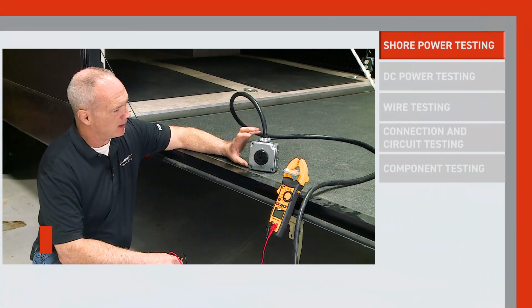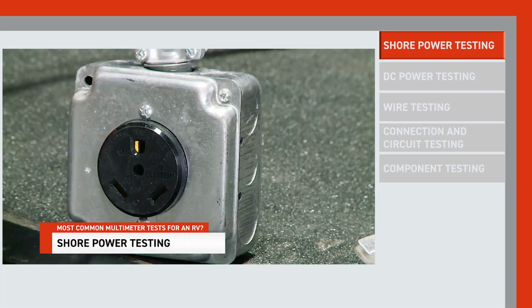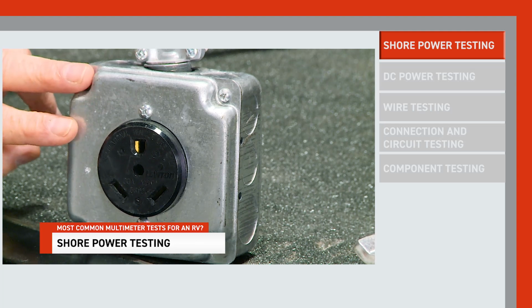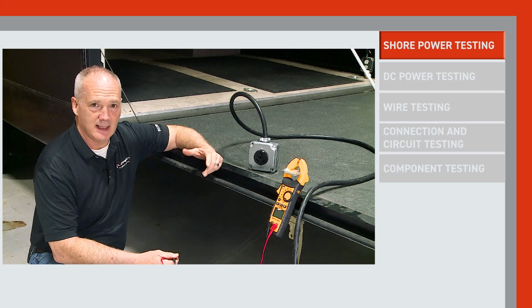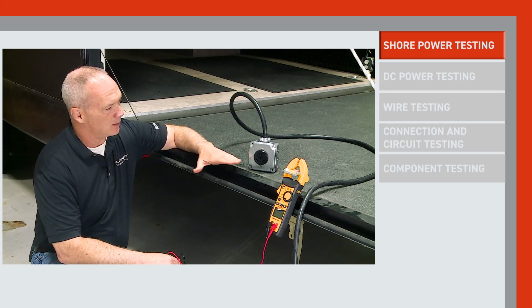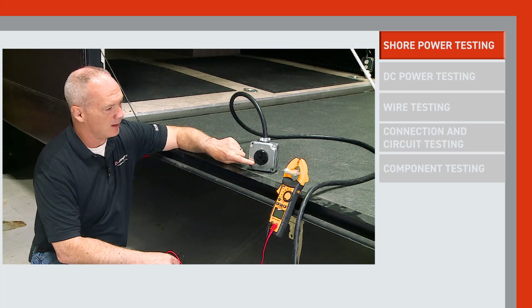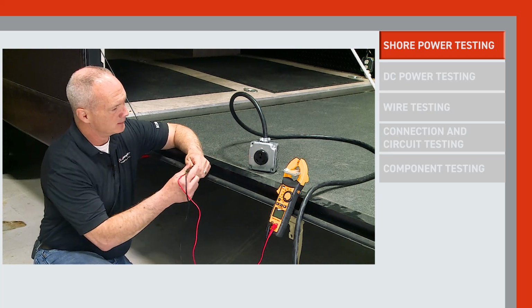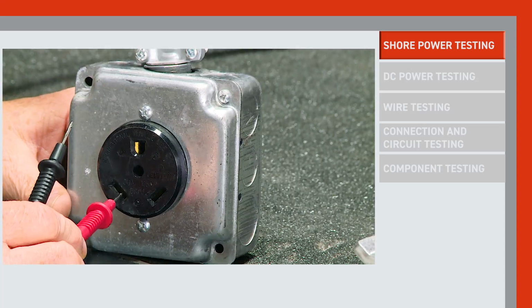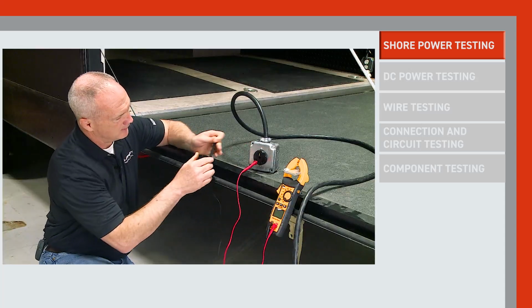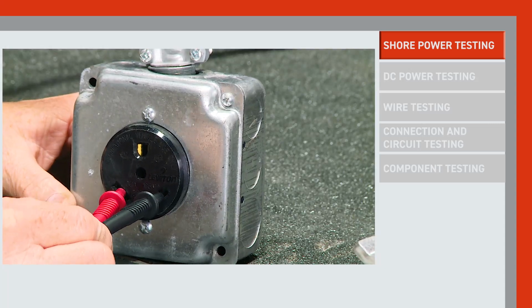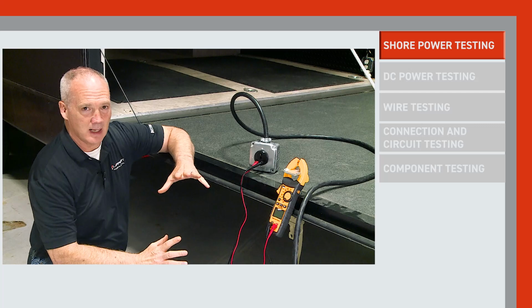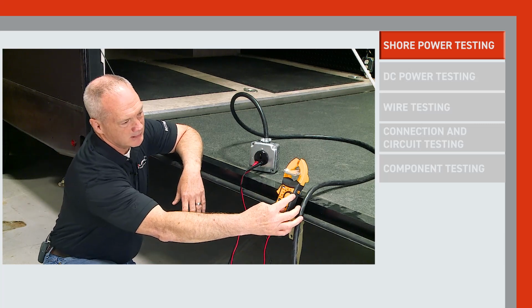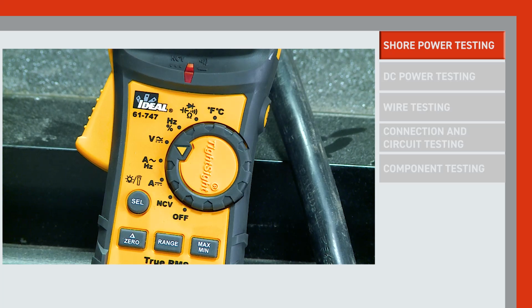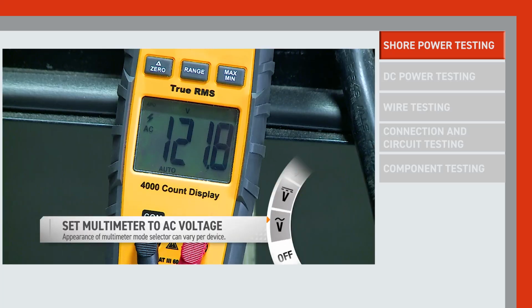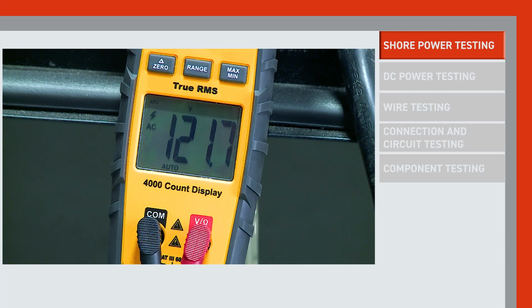Here we have a replica of what a shore power terminal looks like. This is a 30 amp, 120 volt receptacle, just like you'd find at a campsite. I'm going to make this simple and check one area for that 120 volts AC. I'll take the positive lead and put it in this left terminal, and the negative lead in the right lower terminal. Now that those are making contact, I'll take my selector dial and put it on volts, make sure it's on AC, and you'll see 121 volts AC.